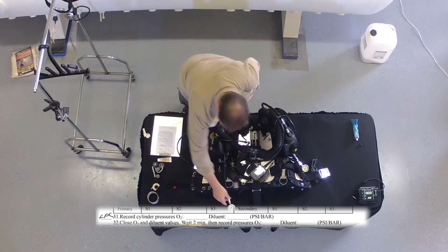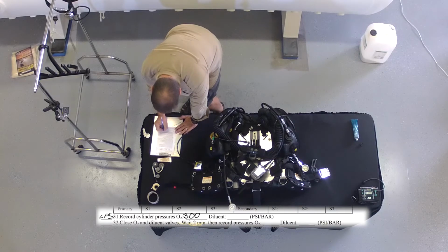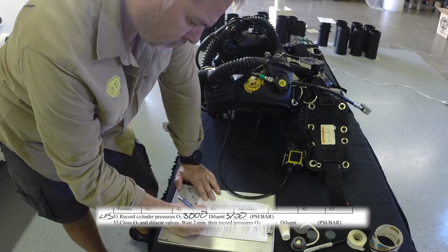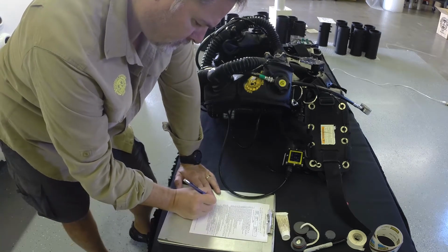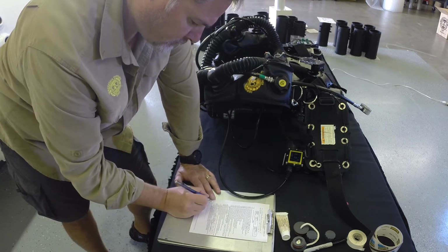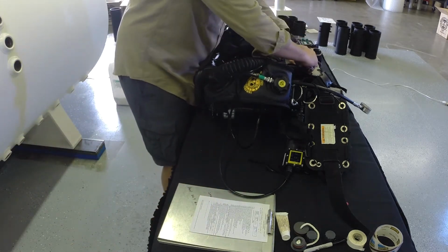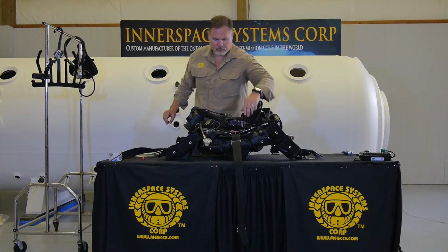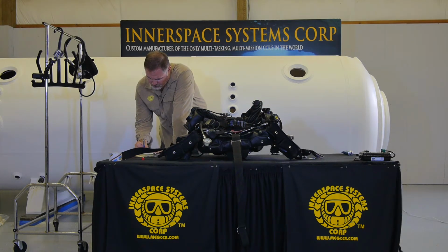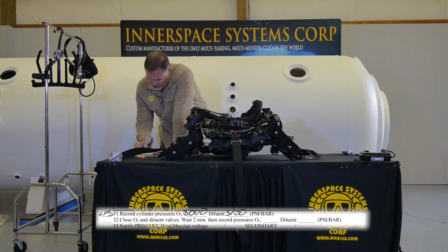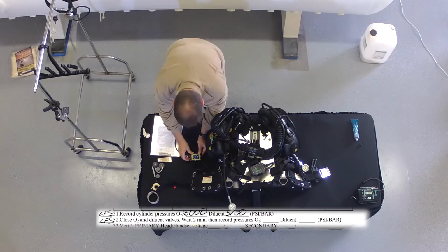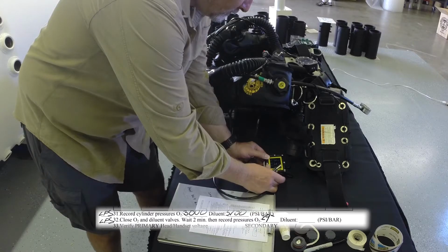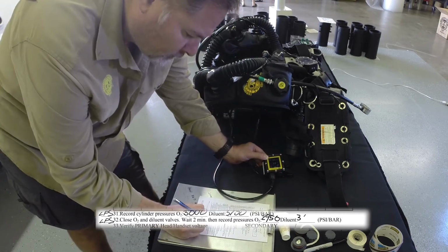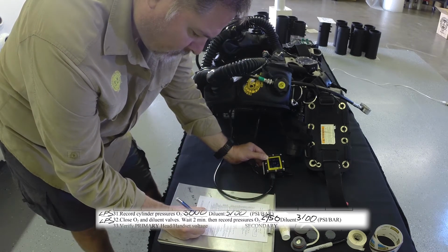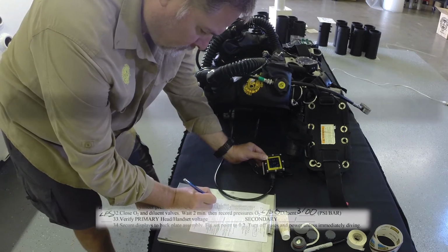Going to step 31, record cylinder pressures. In this case, I have 3,000 PSI on the O2, 3,100 PSI on the dil bottle. And then on step 32 here, close O2 and dil valves and wait 2 minutes, and then record the pressures again. After you know that the pressures are holding, you write them down again. In this case, I had 2950 and 3100. I'm good with that.